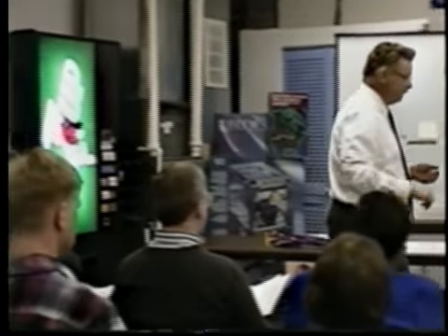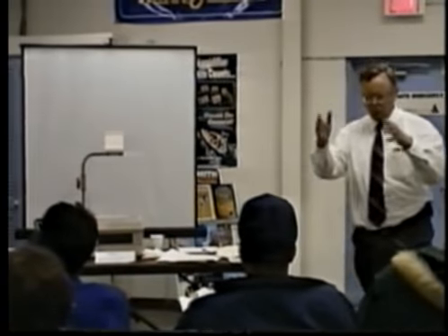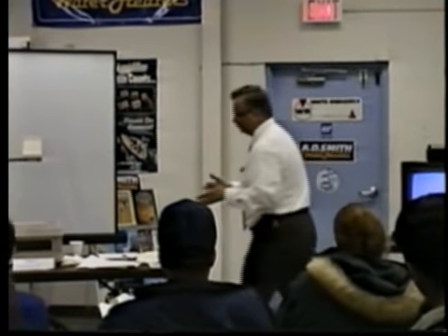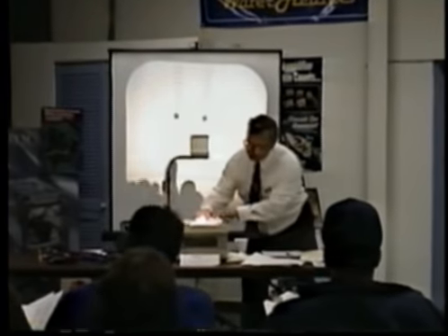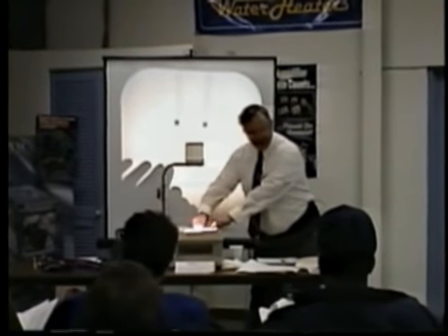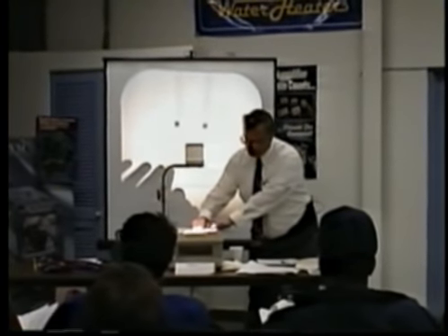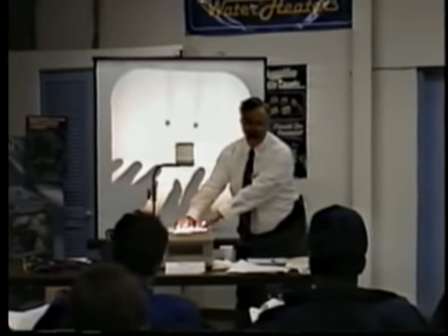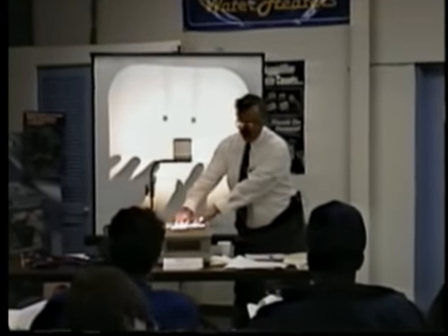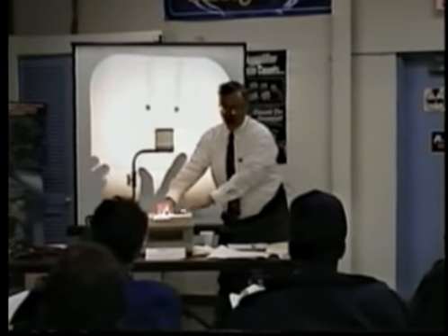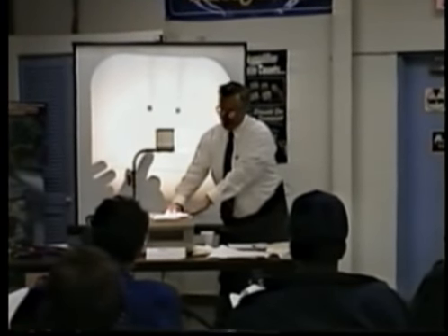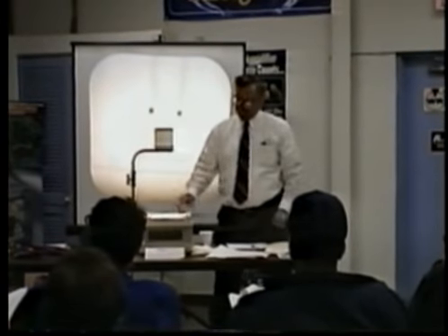And in this business, you have to understand heat pumps. We are seeing them in this area. We're seeing more and more of those, and you better understand it. Because what it's telling you here is that when the air is 0 degrees, it's got 89% of the heat that it had at 100 degrees. You take the same air that's 100 degrees and that's hot to Martin. You make it 0 degrees, that's cold to Martin, but it ain't cold to the heat pump because there's 89% of the heat left.